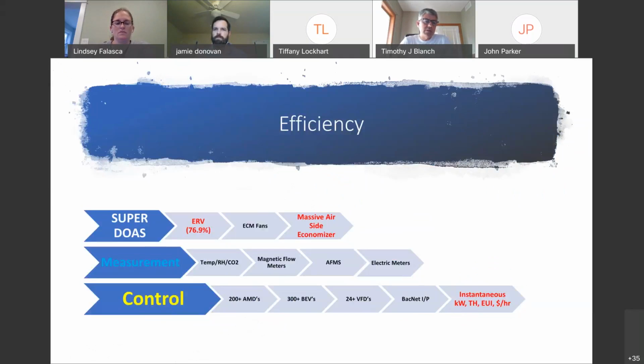We have over 300 Belimo energy valves, which is a BTU meter and a control valve combined. We have a number of VFDs. We use BACnet IP. But maybe most important of all is we have a web page dashboard, whatever you want to call it, which shows you the instantaneous demand in kW and therms, and then also EUI and cost per hour, both in a trailing average on your EUI. So we have converted all of this information into the metrics that we get billed for, that we track our Energy Star ratings for in our EUI, and that has been absolutely necessary for the kind of performance we've gotten here. Next.